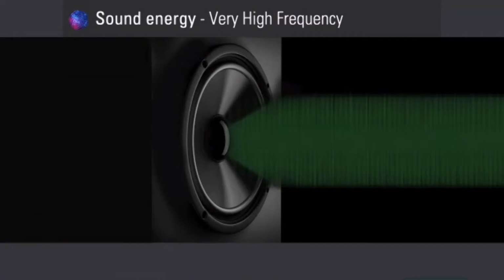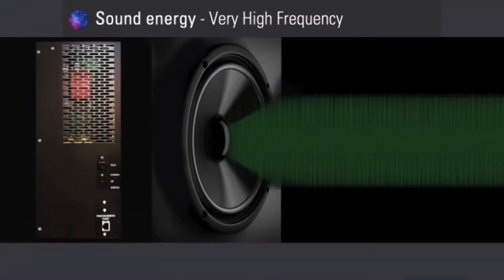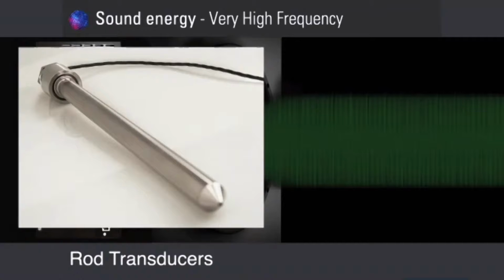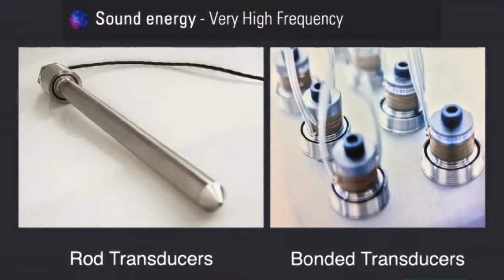Let's talk about the cavitation machine itself, your ultrasonic machine. Now, we've seen instruments, right? A bass guitar and a flute. Here's the generator. That is your musical instrument for your machine. And then you can see the waveform is very high. It's ultrasonic, out of the range of hearing. Of course, you can hear it hissing, but you can't really actually hear or perceive the actual pitch. It's out of the range of hearing. But what's happening? Where does the energy come from, or how is it produced and how is it that it emanates in the basin?